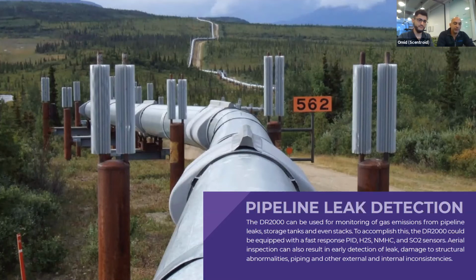The equipment itself, the tablet, has features to set up alarm levels. So you can say, I want PID reaching 100 ppb to give me an alarm, and as soon as it hits that, you will hear an audible alarm from the tablet, like a siren. And you'll know you need to go back and monitor that area in more detail.